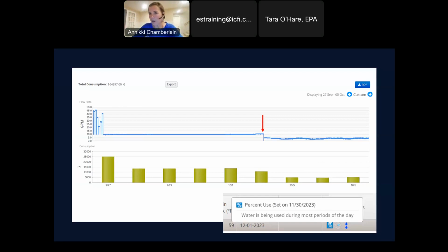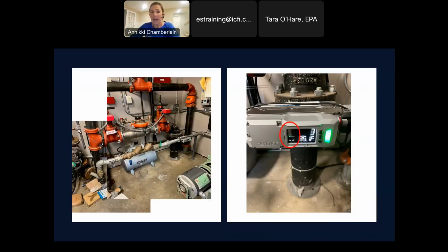Again, I see a big water drop. So I'm like, okay, did you guys find something now? He said, no, we totally shut the irrigation system off. And I'm like, oh, well, interesting, because you've still got water running. So we go back, we open the, we test the backflow, and it does still have pressure. So basically this gate valve here had not closed all the way. So even though the system, they turned it down, wasn't closed all the way. In this picture, the ball valves are closed, but this was after the fact. So they were able to close the ball valves and verify that the system was off, but that would have basically been running water into the irrigation system all winter.